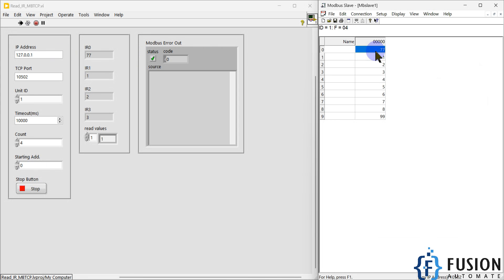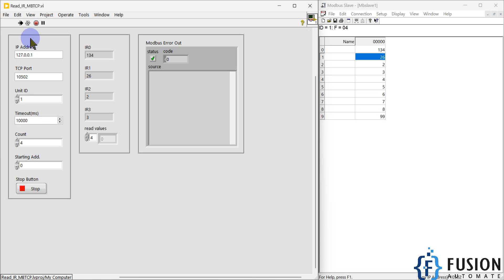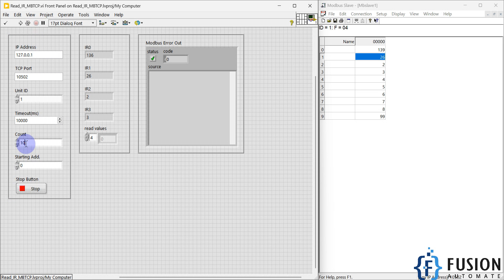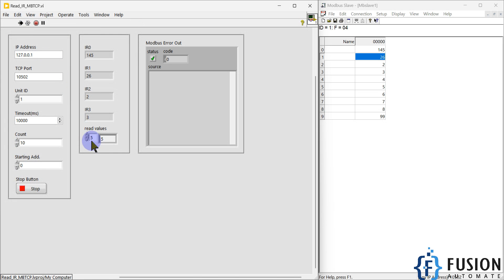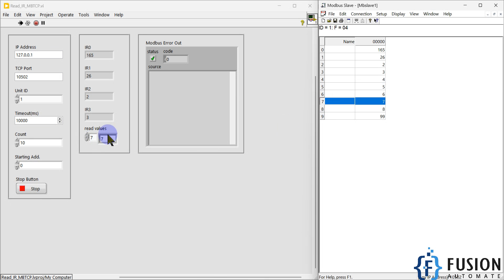It is reading the input register data from my Modbus TCP simulated device. If I change the value of input register 1 to 26, you can see it is reading the updated data. I can also read data from input register 0, 1, 2, 3, and 4. Since I am only reading 4 input registers, I need to increase the count. I can increase the count to 10 and run the project — so for input register 5 I have value 5, register 6 has 6, register 7 has 7, register 8 has 8, register 9 has 99.